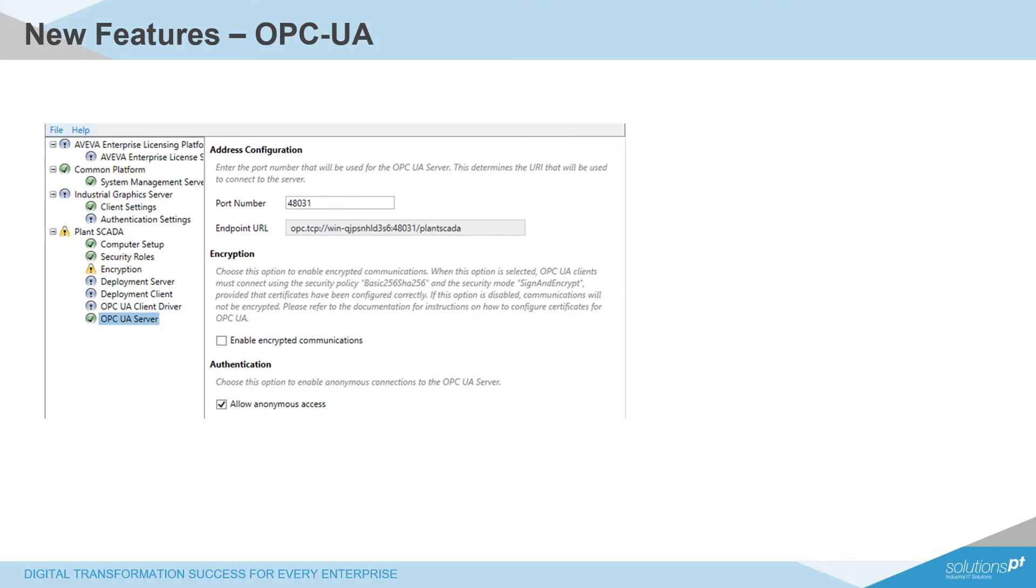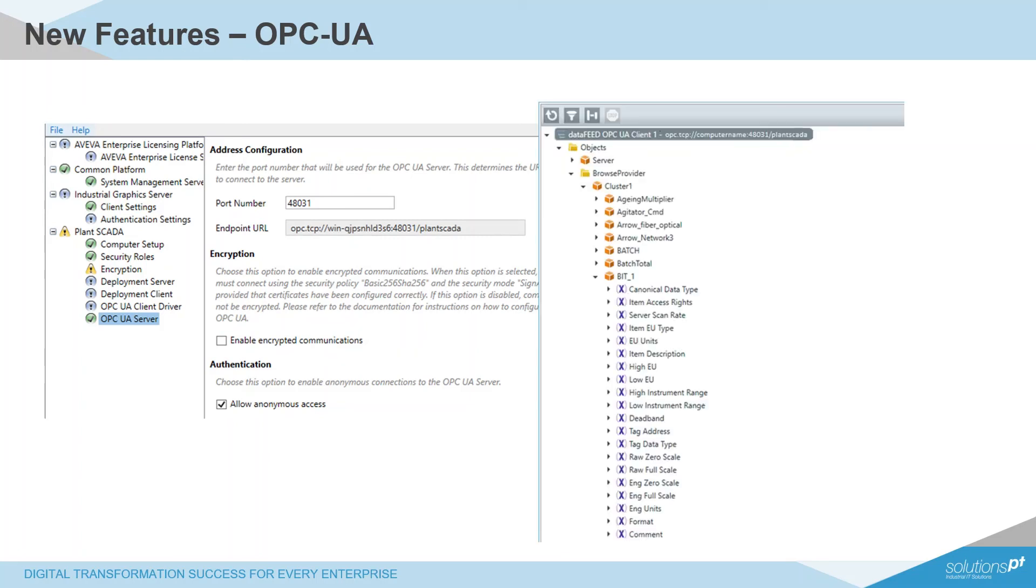Note that in this release, this support is limited to tags only, so OPC UA alarms, conditions, and historical access support are planned to be included in future releases. You can also enable encryption in here with Basic 256 SHA 256 or enable anonymous access for testing purposes.